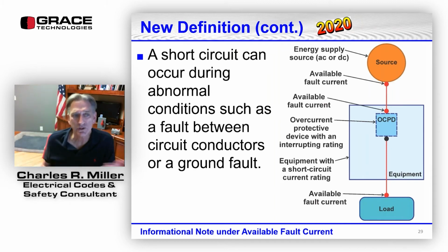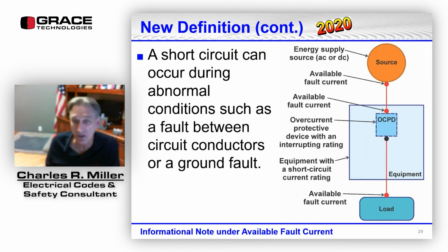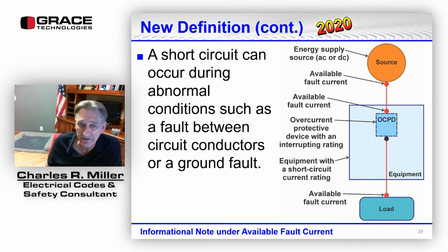A short circuit can occur during abnormal conditions, such as a fault between circuit conductors or a ground fault. So in the illustration on the right, we have an energy source. The available fault current is coming out of that. Available fault current is right before the overcurrent device. The equipment itself has a short circuit current rating, SCCR rating. The overcurrent protective device is the one with the interrupting rating. And it's also on the bottom showing the available fault current on the load side of the overcurrent device that's going to the load. So here's another example.